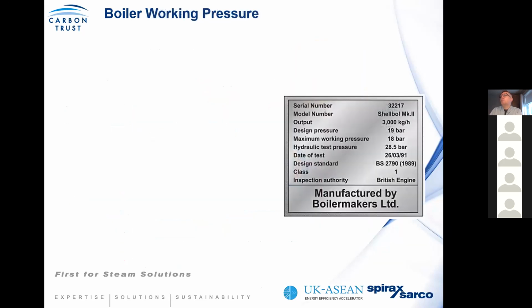Okay, we mentioned earlier about boiler working pressure. So you'll see from this nominal boiler nameplate that the boiler is designed for 3,000 kgs an hour with a design pressure of 19 bar, but a maximum working pressure of 18 bar.